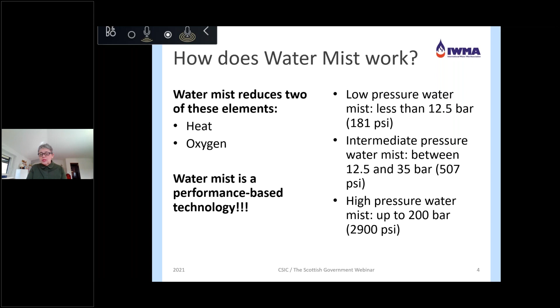When it comes to the definition of the different water mist systems, you can see on the right-hand side that low pressure systems work with a pressure below 12.5 bar. High pressure systems work with a pressure above 35 bar, and systems ranging between these two figures are defined as intermediate systems. Now, this is according to two North American standards, FM 5560 and NFPA 750. These two standards were published about a quarter of a century ago, and just over 5 years ago, VDS published their guideline 3188. In there, it says that there are basically just two systems: low pressure systems that remain below 16 bar or 232 psi, and high pressure systems that exceed 16 bar. What may also be interesting for you is that low pressure water mist systems are obviously much closer to traditional sprinkler systems than, for example, high pressure systems, and that sprinkler components can be used.